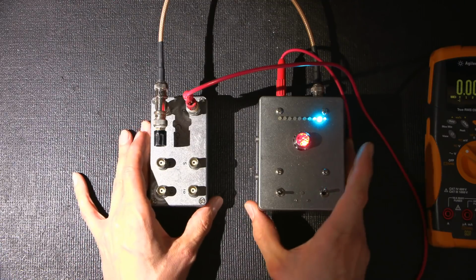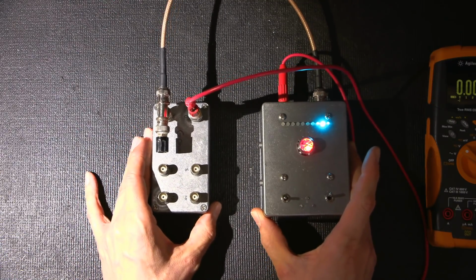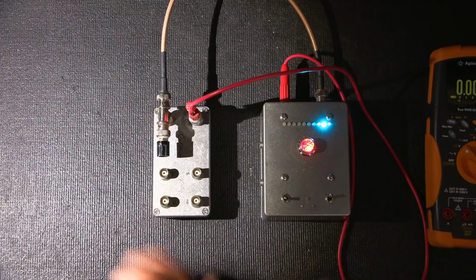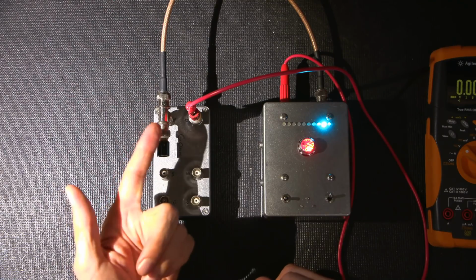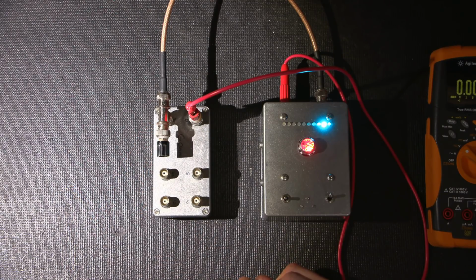So very, very sensitive device. And this is the reason that any type of issue with the circuit board, even if you have a piece of FR4 board that's leaky, or it's been moist, or anything like that, when you're dealing with 40 billion ohms of leakage resistance, it's going to pretty much see that. The new one is going to be even more sensitive.